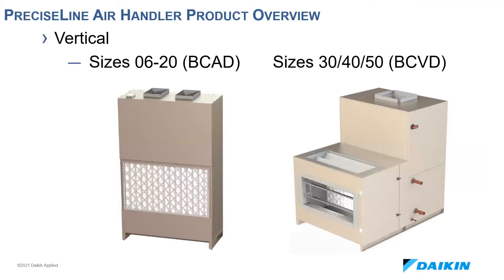The vertical configuration fits through a standard door as well. The BCAD, or apartment design, is only 18 inches deep and will fit in a closet. Discharge plenum is available on all sizes, and mixing box is available on the larger units. Coil access on the BCAD is from the front, with field piping access holes available on both sides and back of the cabinet. Coil access is to either side on the larger units.